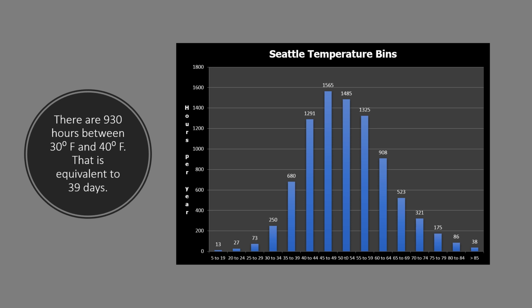Let's see what it says for Seattle. Seattle, as we all know, is a much warmer climate than Boise, but there are still 930 hours, and that's the equivalent of 39 days. So that's one of the reasons the program really pushes for that lower 30-degree balance point, because so many places in the Northwest spend a lot of hours between 30 and 40 degrees every winter.